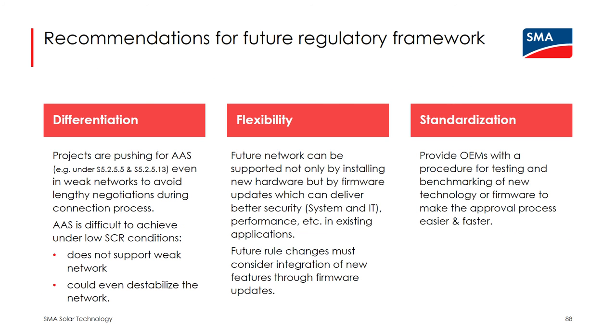And to wrap up what I just showed you, here are some recommendations I would like to give. Based on the SMA experience, with regard to the regulatory framework, it would be a good idea to consider some kind of differentiation of what SCR level generators are going to be connected to. If the SCR is quite low, whatever a good value might be, maybe below 2, it would be a good idea not to try to tune the system to achieve automatic access standard, because this kind of aggressive tuning does not really support the network under those low SCR conditions, and it could even destabilize the network.